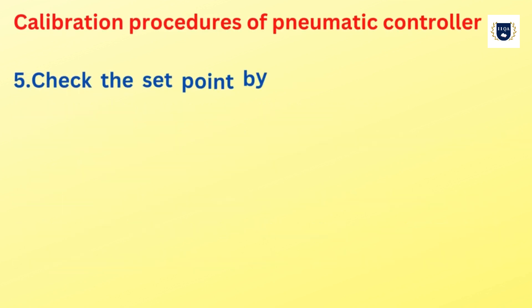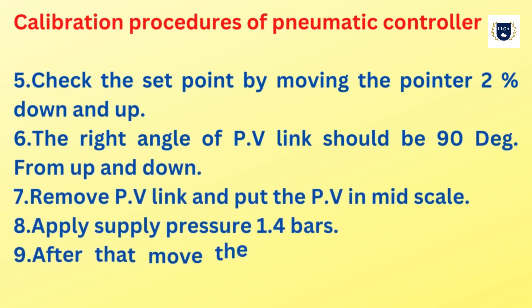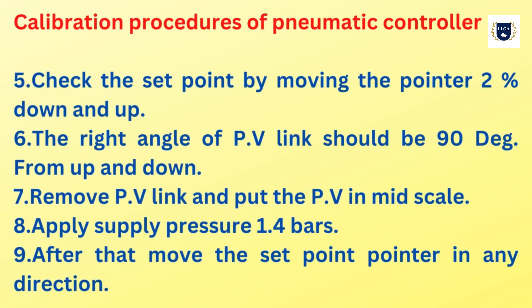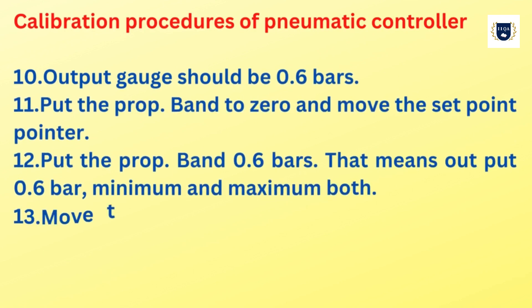Check the set point by moving the pointer up and down. The right angle of PV link should be 90 degrees from up and down. Remove the PV link and put the PV in mid-scale. Apply supply pressure 1.4 bars. After that, move the set point pointer in any direction. The output gauge should read 0.6 bars.